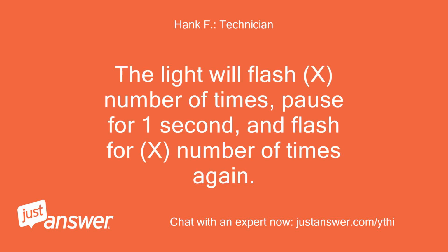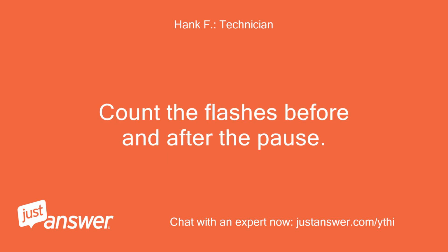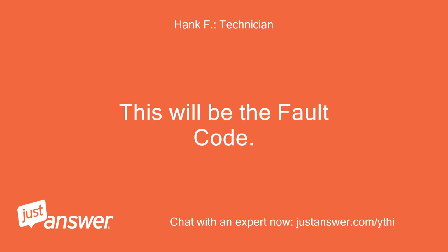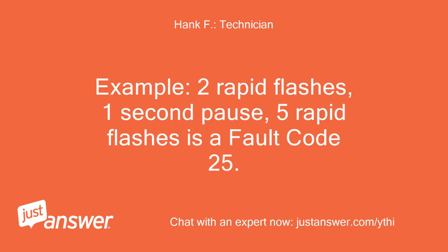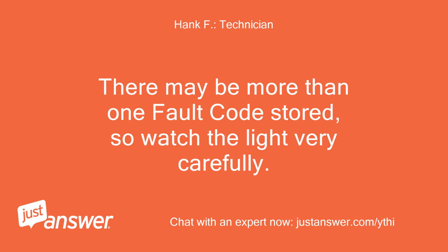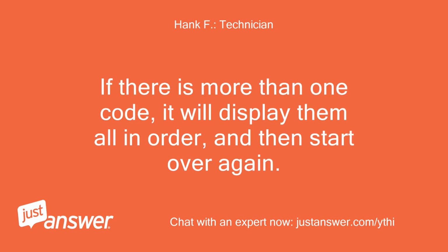The light will flash X number of times, pause for 1 second, and flash for X number of times again. Count the flashes before and after the pause. This will be the fault code. Example, 2 rapid flashes, 1 second pause, 5 rapid flashes is a fault code 25. There may be more than one fault code stored, so watch the light very carefully. If there is more than one code, it will display them all in order, and then start over again.